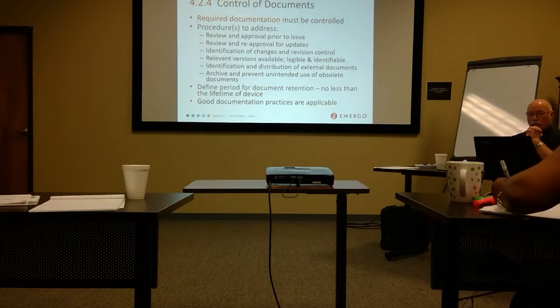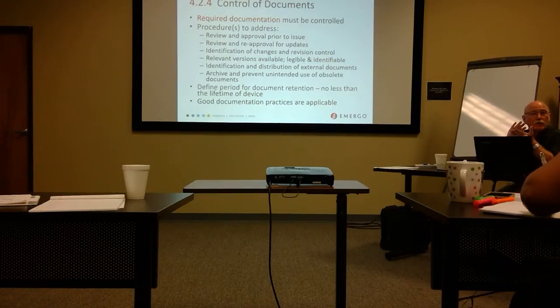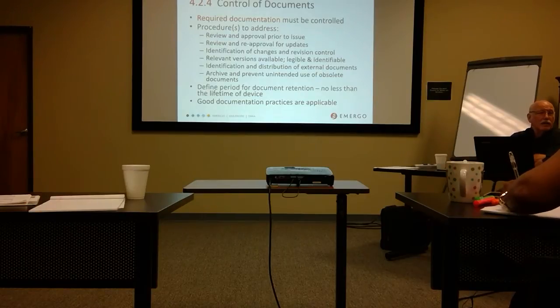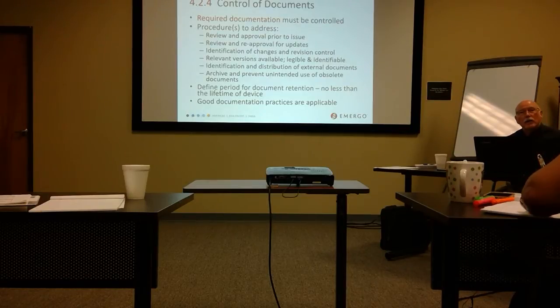Doc control is a critical process. Much of this appears in change control, but review and approval of your procedures prior to issuing them is a critical factor, and the folks that do that should be the subject matter experts. For revision, it needs to be the same, not necessarily the same individuals, but the same function that approved the original version. That's actually in the standard itself. It's also on the FDA side. Identification of changes in rev control. We already touched on this. These documents should all carry rev numbers. Doesn't matter how you do it. A, B, C, D, E, F, G, 1, 2, 3, 4, alpha, beta, gamma, delta, I don't care. Makes no difference, as long as you can identify one rev from the next. Critically important.